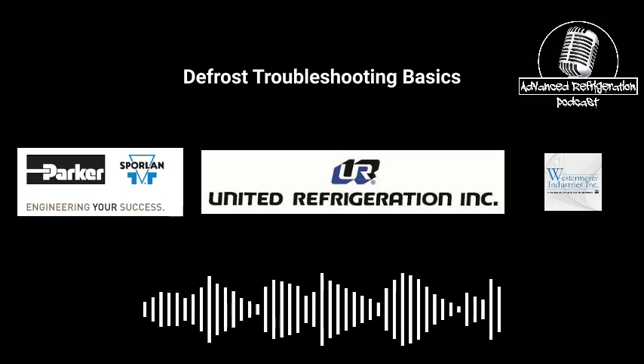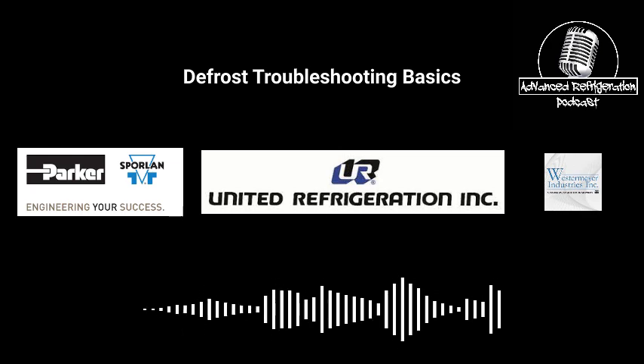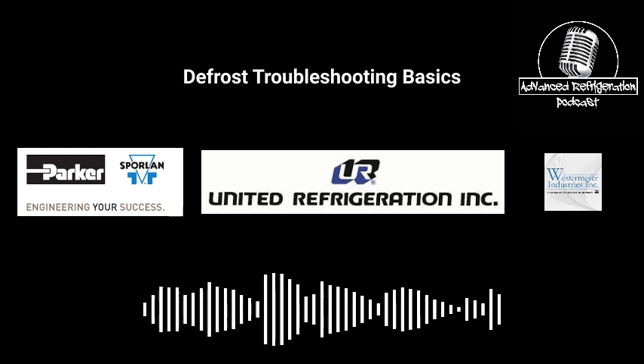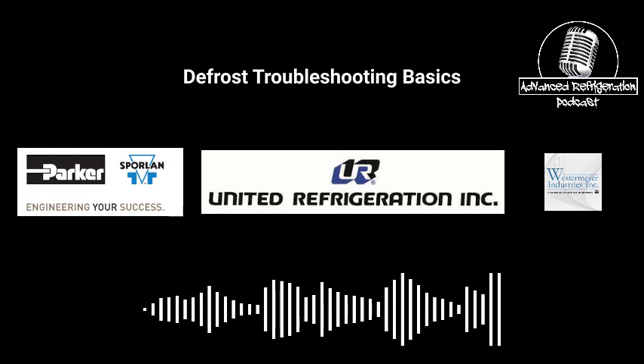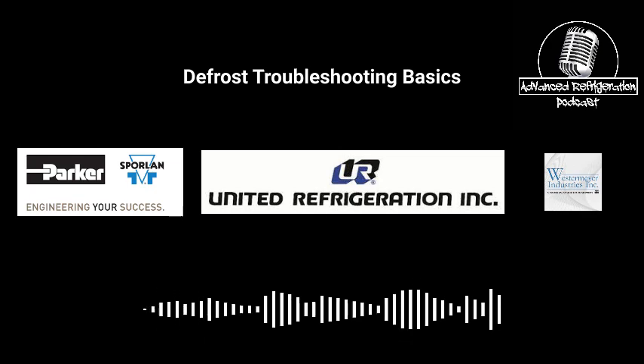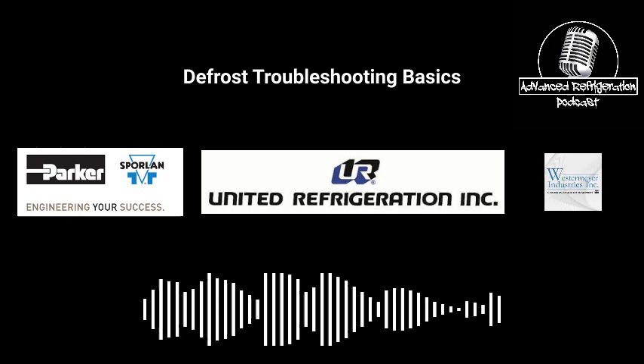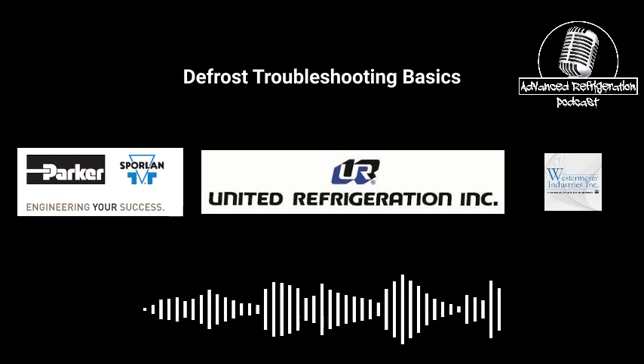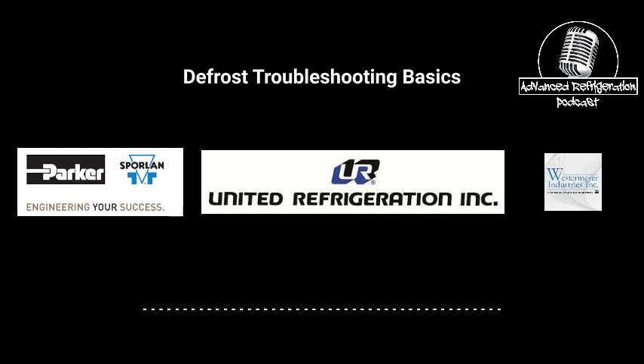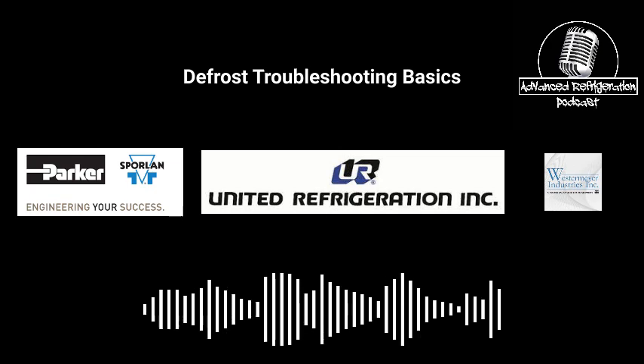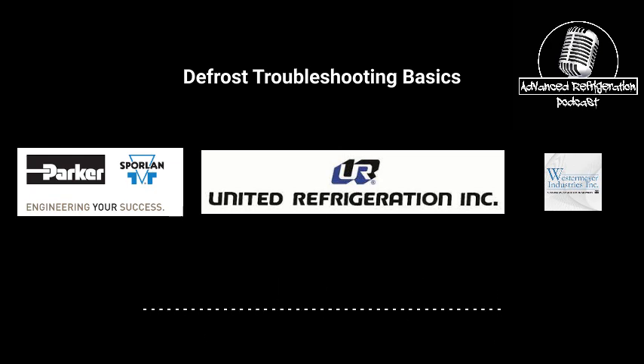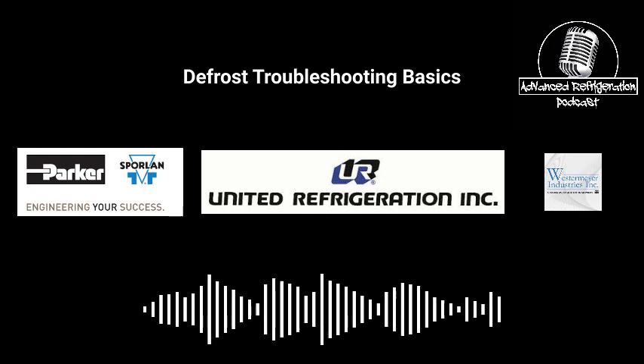Yeah, and do you want to talk about sensor placement, where preferably you would like to have the sensors? I can touch on that if you want. So sensor placement, guys, everybody does this differently. All the customers do it differently. Electric defrost, if it's a coil, I like the bullseye method, which is usually the second or third fan from the TXV side, and I will mount it about 3/4 of the way up on the face of the coil. That's where I want it. I want it away from the heaters, and somewhat close to the TXV side.